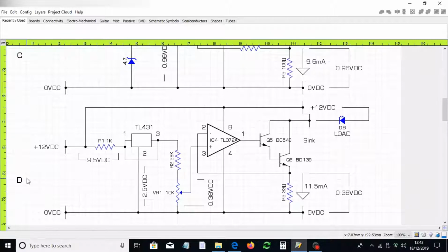The chemical cell, the Weston cell, was not built to provide current the way we kind of know it as, let's say, a AA type battery, where the object is to draw current from the cell to drive, say, an LED. A reference cell, Weston cell, is not that type of structure. It is not designed to provide current.